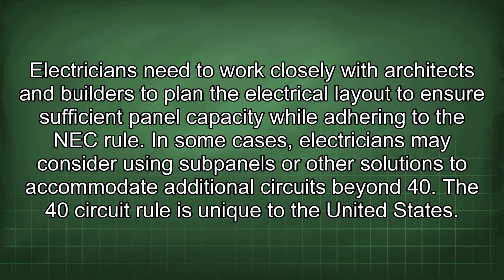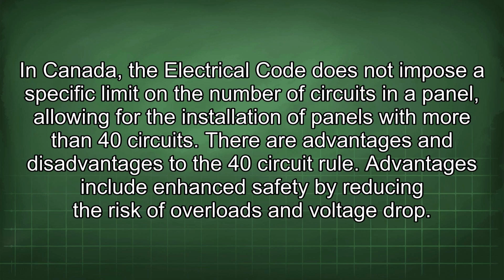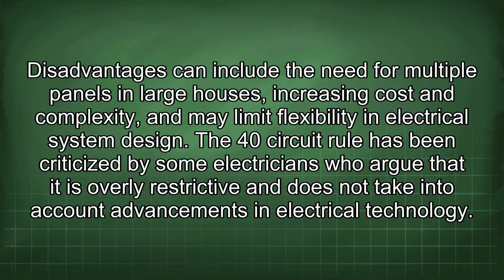The 40 circuit rule is unique to the United States. In Canada, the electrical code does not impose a specific limit on the number of circuits in a panel, allowing for the installation of panels with more than 40 circuits. There are advantages and disadvantages to the 40 circuit rule. Advantages include enhanced safety by reducing the risk of overloads and voltage drop. Disadvantages can include the need for multiple panels in large houses, increasing cost and complexity, and may limit flexibility in electrical system design.